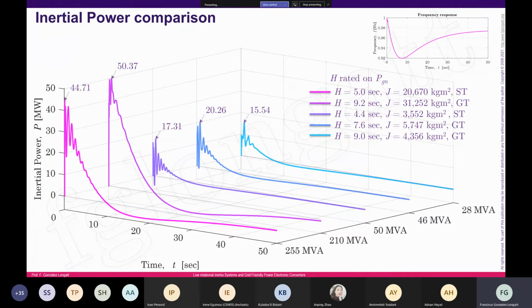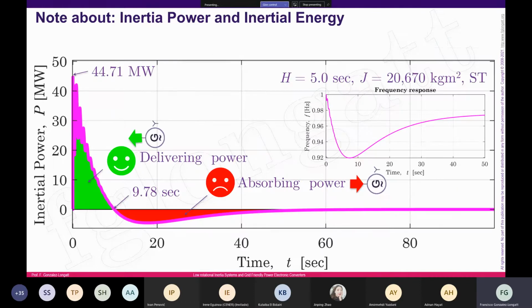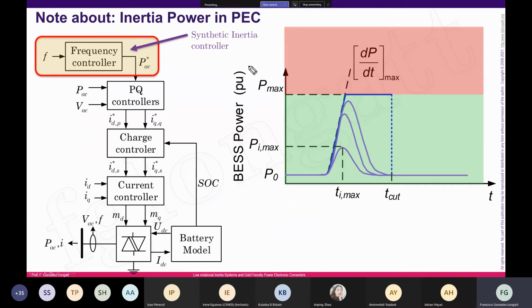The inertia power is basically the active power contribution that is produced when the frequency changes at the stator of the synchronous machine. And as you can see over there, depending on the rotational inertia, you have different peaks for the inertia power, okay? But what is the problem about inertia power? That the inertia power is connected to the inertia energy.